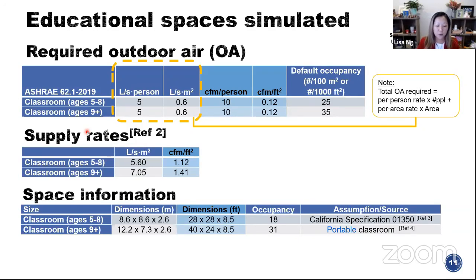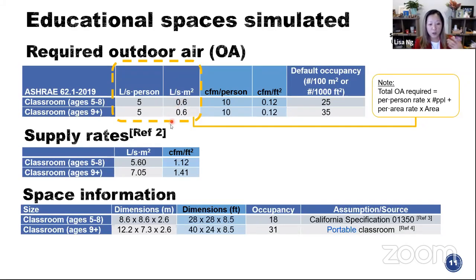We took ventilation rates from ASHRAE 62.1-2019 — the ventilation standard for commercial buildings — and looked at two classrooms: one for younger kids ages five to eight and one for kids ages nine plus. Their liters per person and liters per square meter criteria are the same; the only difference is that the default occupancy is different — there are more people in the ages-nine-plus classroom. The total required outdoor air ventilation rate is a per-person number times the number of people plus a per-area number times the area. We also found typical supply rates in ASHRAE 62.1's informative annex, though these are not required. The two spaces are based on a California specification for emissions and a portable classroom in an ASHRAE journal.